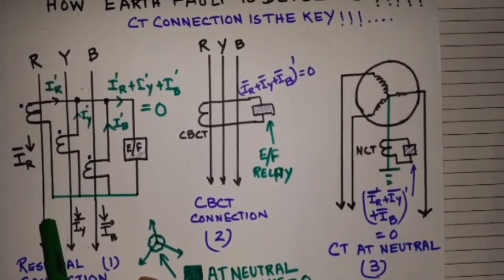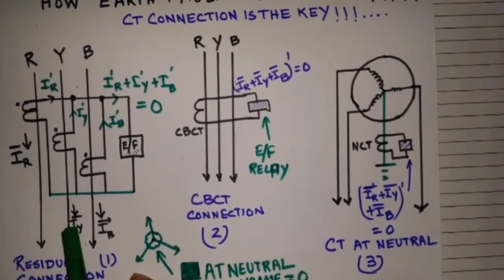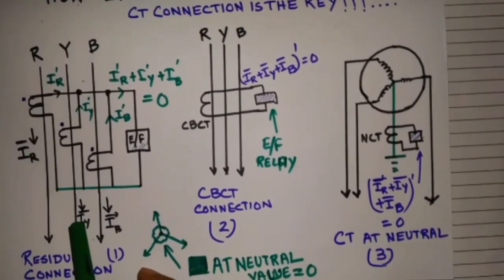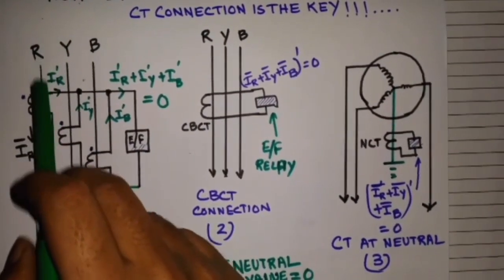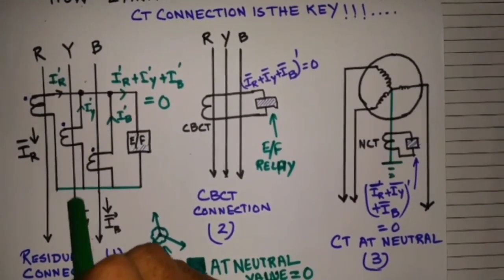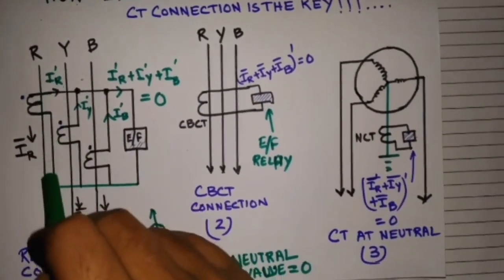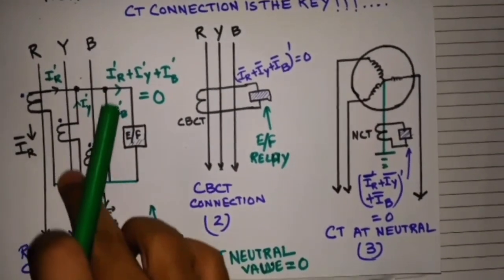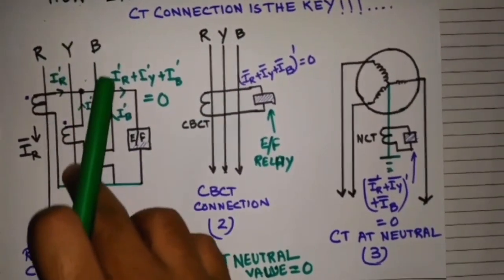But if there is a fault between IR and IY, a line-to-line fault, then the current will come through IR to the faulted path and it will return back through IY. So again, if IR is in this direction, IY will be in that direction.